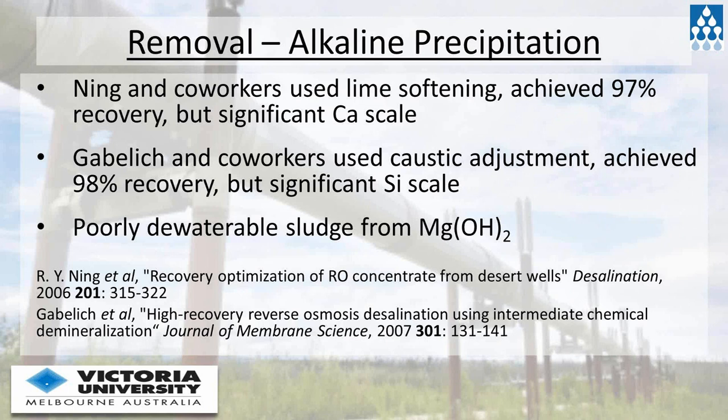Ning and co-workers, who is ultimately Tony Tarquin's research group, have used lime softening and they achieved a 97% recovery doing this. However, they had a significant amount of calcium scale because there was significant calcium residual within their water. So while they were getting a 97% recovery, they were scaling up their membranes rather quickly.